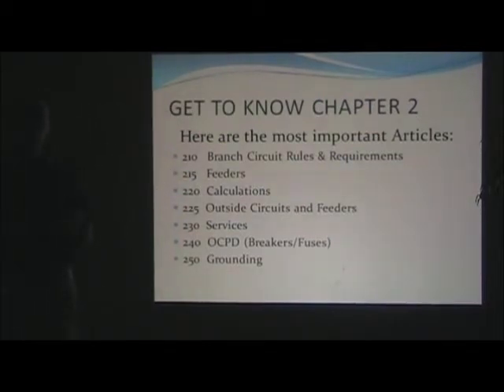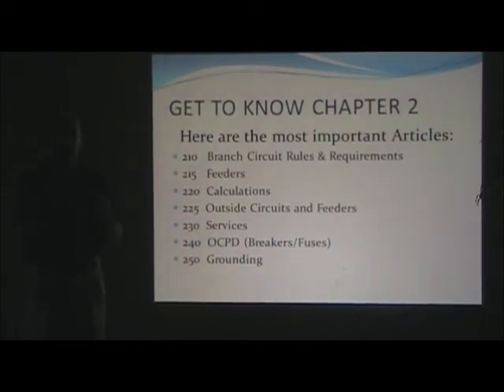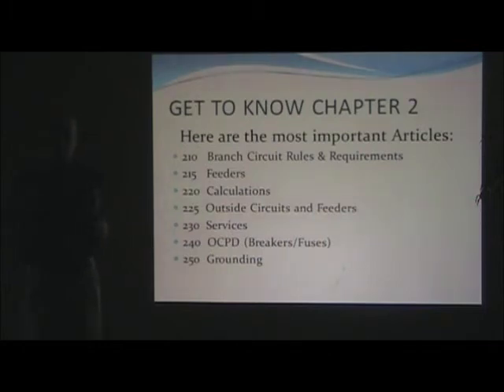A separately derived system is a service that is separated from another service and must, by its own definition, have its own grounding and bonding rules. A transformer is a perfect example - when you transform a voltage class from 480 down to 240 volts, you have two windings separated around the core. That inductive reactance between the primary side and secondary side causes the voltage to step down, but the two windings are physically separated from each other.